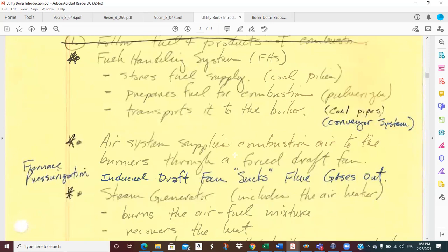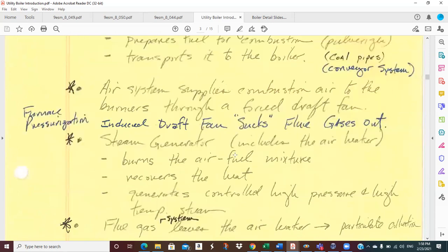Good, thank you. Okay, air systems, we talked a little bit about that. We've got our furnace pressurization. We went through that last time. You've got a FD fan, a forced draft fan that blows into the boiler. And you've got an ID fan, an induced draft fan that sucks out of the boiler.